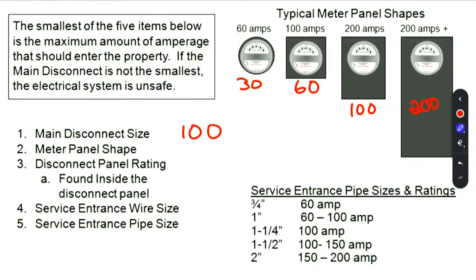Let's say we had this square A box right here, that's going to be the meter panel shape, and let's say that's 60 amps instead of 100. The disconnect panel rating is going to be found wherever the main disconnect is located, either on the dead front cover or off on the sides. I like to take a picture of that and see what it's rated at. Let's say that was rated for 150 amps.